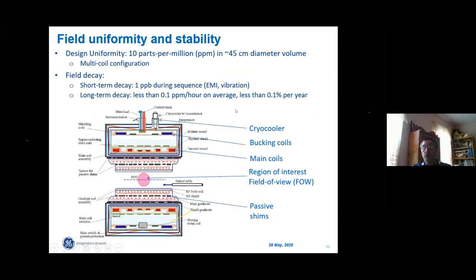Let's talk about requirements for MRI. Again, remember that the magnet is only a component of the system. Uniformity here in the field of view, which is approximately 45 to 50 centimeter diameter in standard magnets, is 10 parts per million in the delivered system. How do we achieve it? We use multi-coil configuration. Here it's a typical 8-coil configuration. We may have more coils in longer, in shorter magnets.